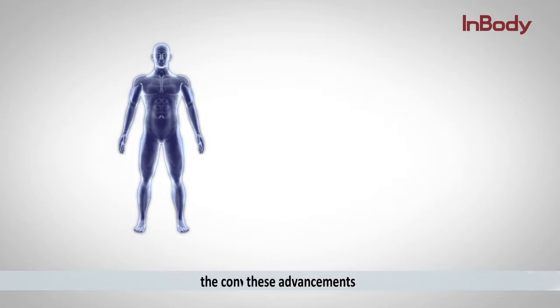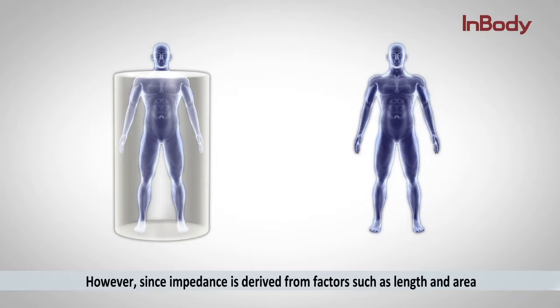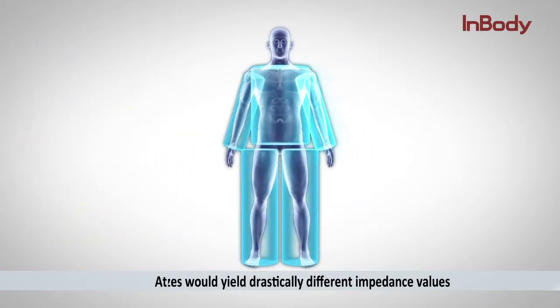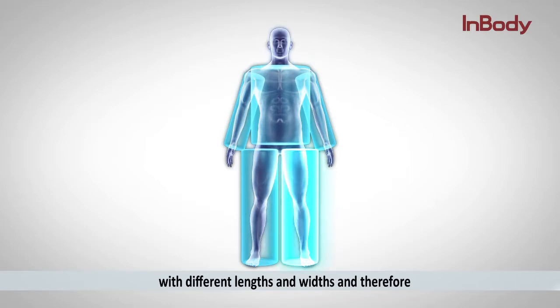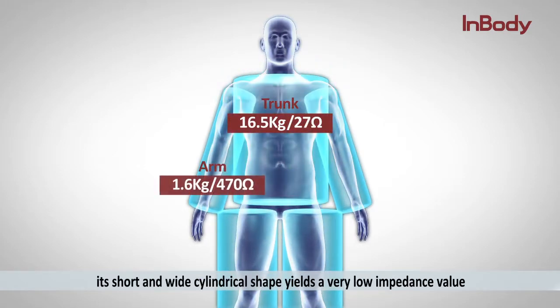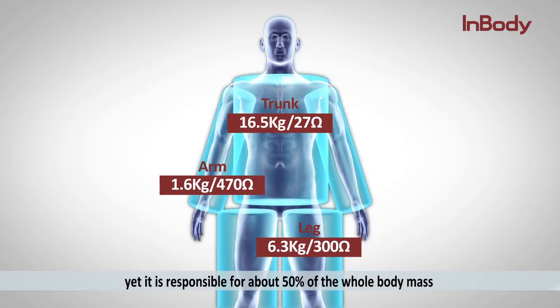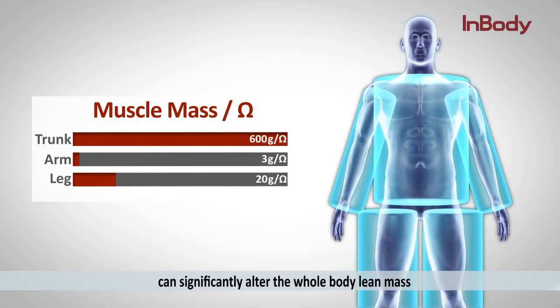Prior to these advancements, the conventional BIA method considered the human body as one cylinder and only offered a single whole-body impedance value. However, since impedance is derived from factors such as length and area, different sizes yield drastically different impedance values. At a closer look, our body is not one but five cylinders with different lengths and widths, and therefore measurements should be segmentally analyzed. Furthermore, the trunk's short and wide cylindrical shape yields a very low impedance value — it accounts for only around 5% of whole-body impedance yet is responsible for about 50% of whole-body mass, meaning even a small change of one to two ohms in trunk impedance can significantly alter whole-body lean mass.